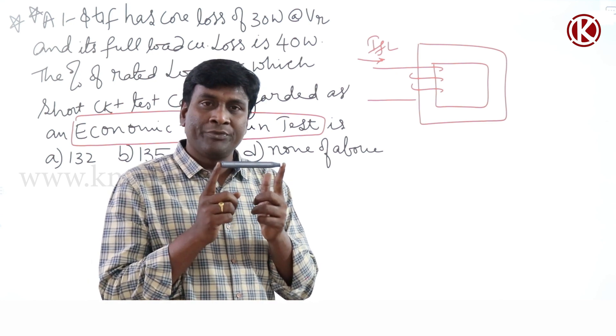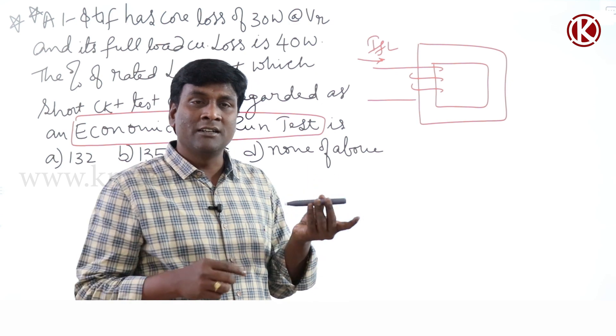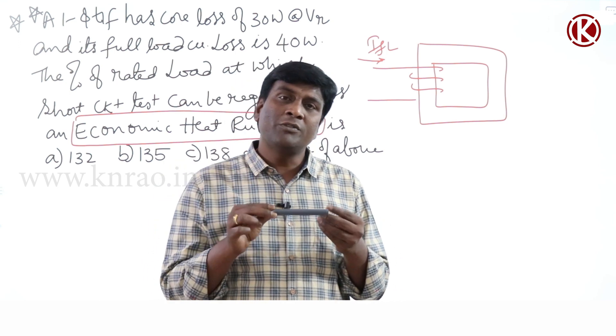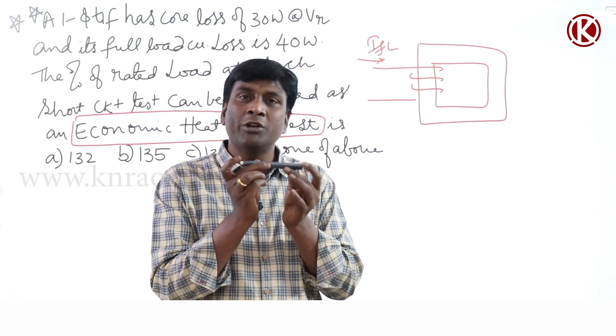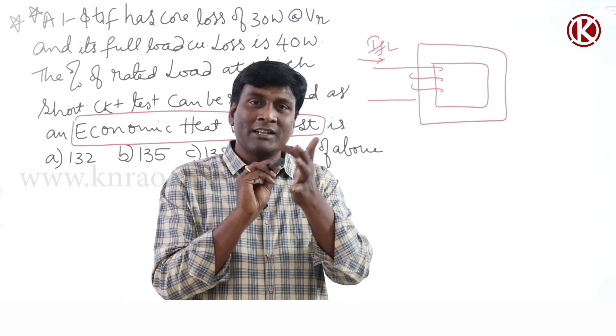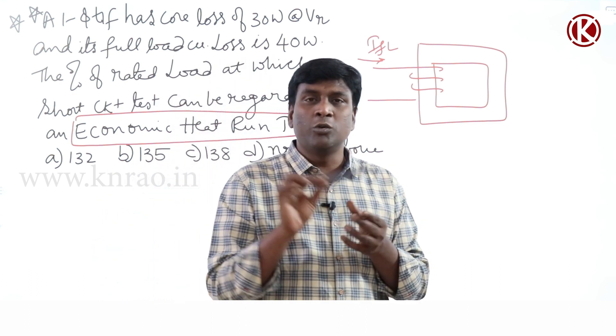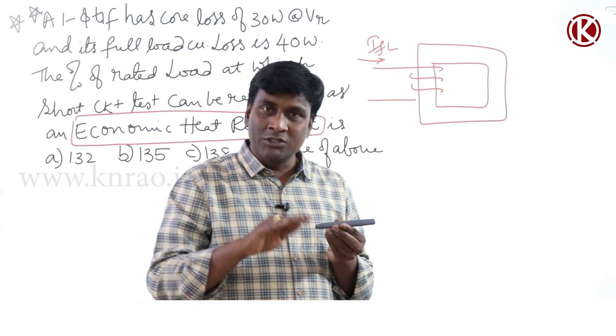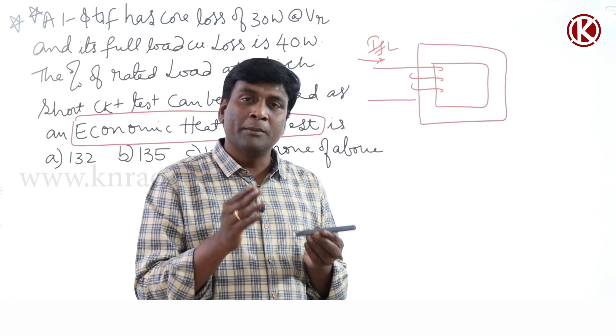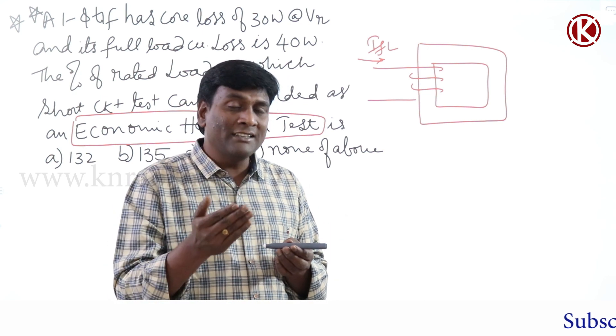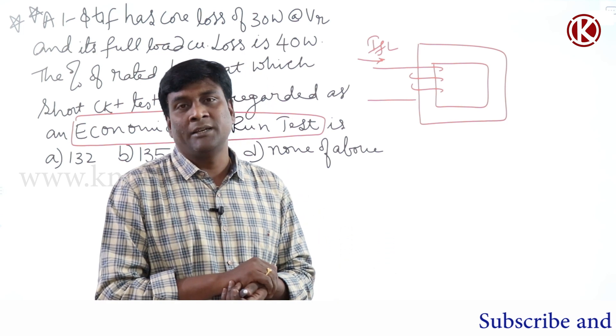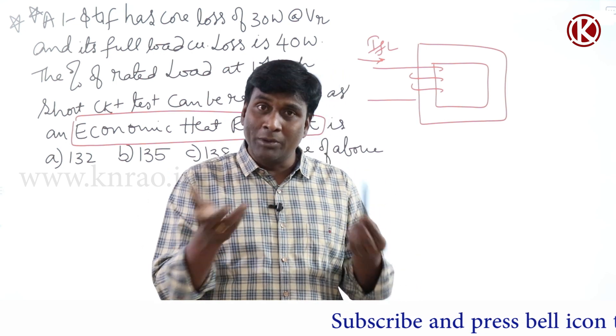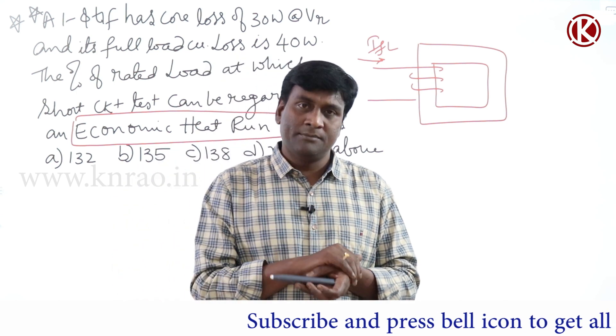For example, consider a copper wire. This area of cross section is designed for 10 amperes. If you inject more than 10 amperes through this conductor, because of the current flowing, there is resistance depending on the length, area of cross section, and resistivity of the conducting material. If you inject current, I²R losses will happen — those copper losses will be converted into heat energy, causing temperature rise, which can burn the conductor if it exceeds the melting point.